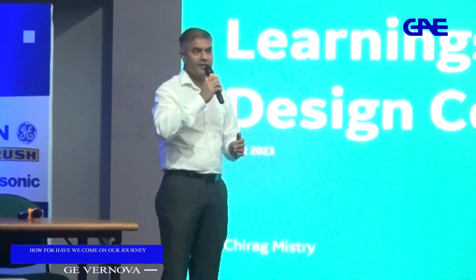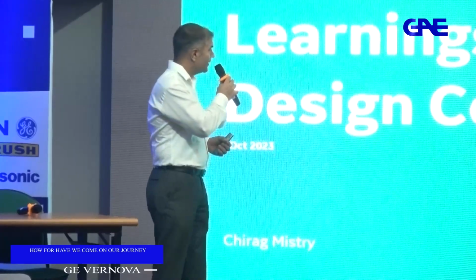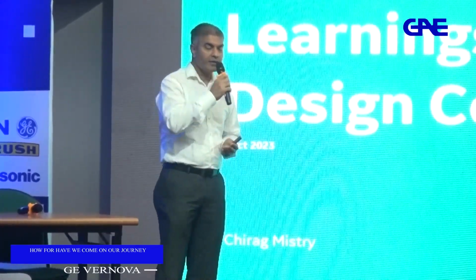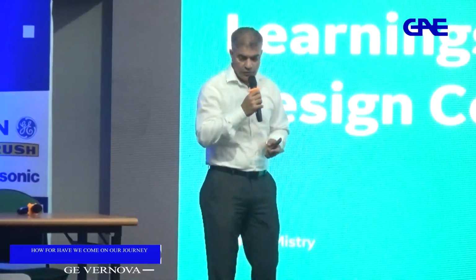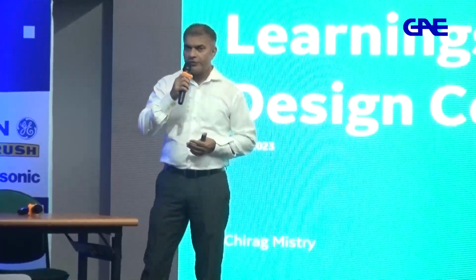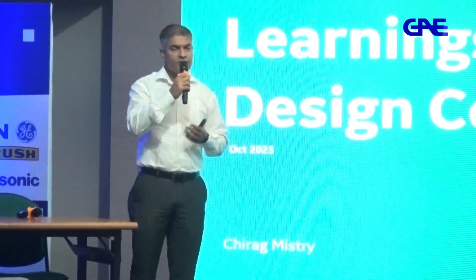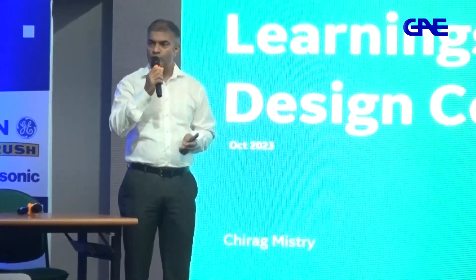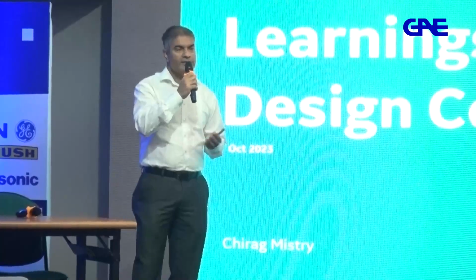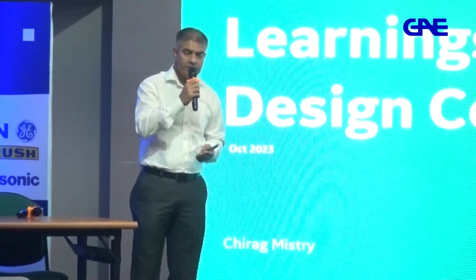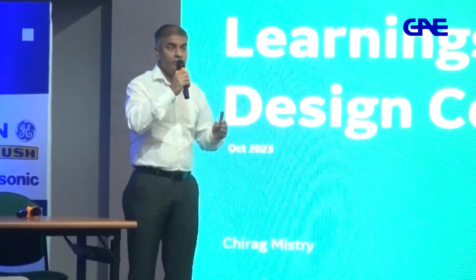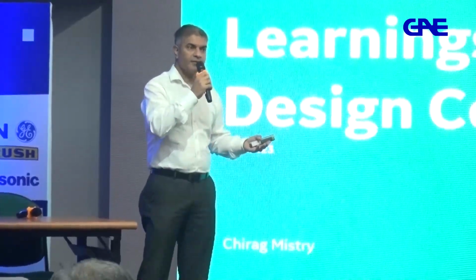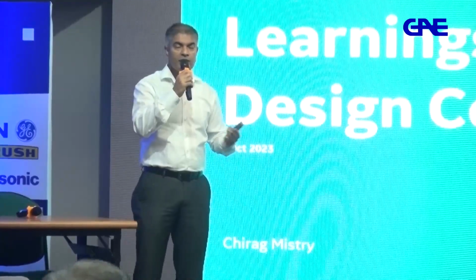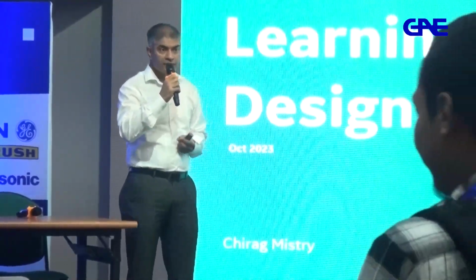In this presentation, I wanted to talk about digital substations, some of the learnings we have made, and some of the design considerations. The concept of digital substation, IEC 61850 station bus, process bus, is not exactly new. We have been talking about it for quite some time. We had our digital substation pilots more than 15 years back, and since then we have implemented so many substations. As GE, we have more than 100 substations, either at the pilot stage or real substations, but much more than 100 that we have had experience with.